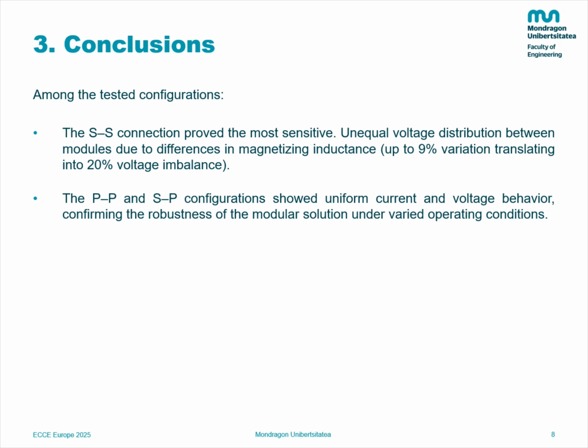Finally, here are the main conclusions. Among the tested configurations, the series connection proved to be the most sensitive, showing an unequal voltage distribution between modules due to the differences in magnetizing inductance. A 9% variation in the magnetizing inductance could be translated into a 20% voltage imbalance. While this did not degrade performance at the tested power levels, it may pose limitations in higher power applications.